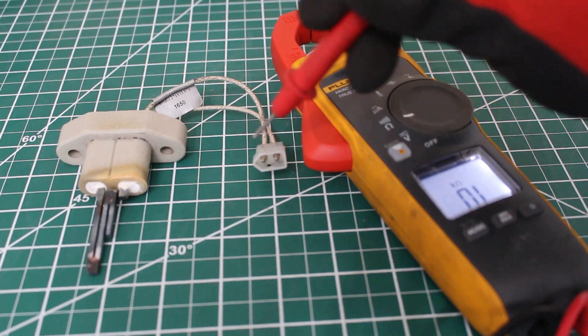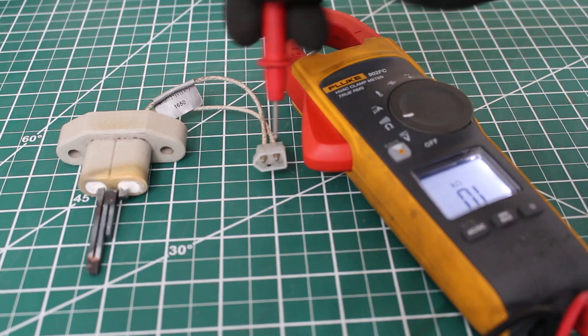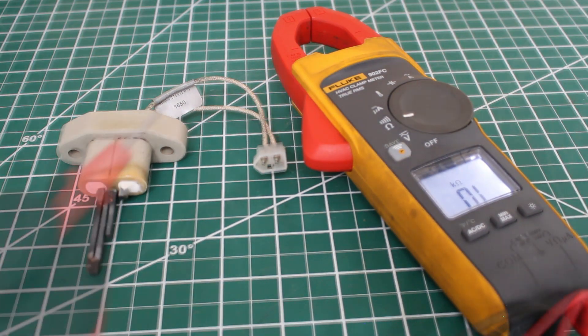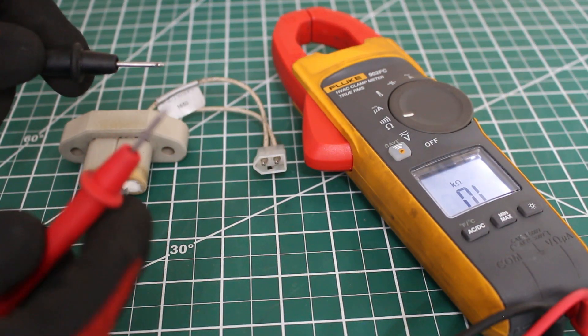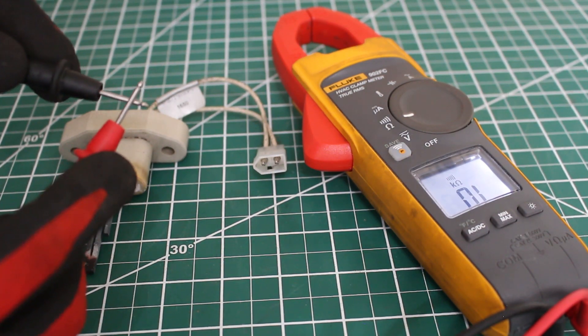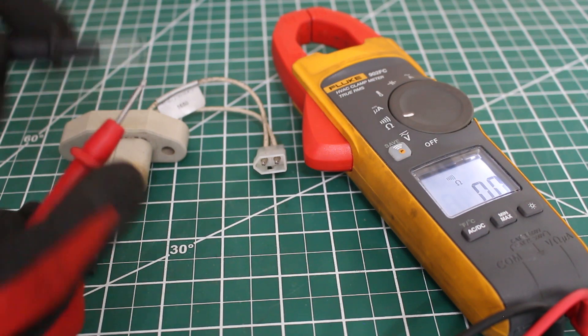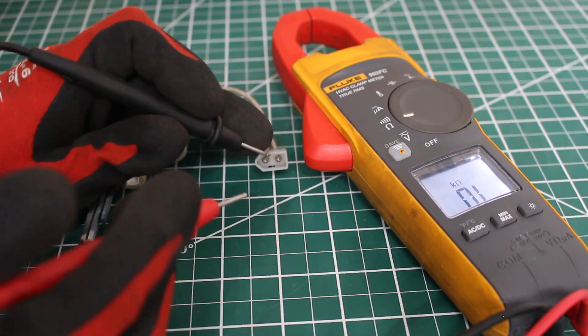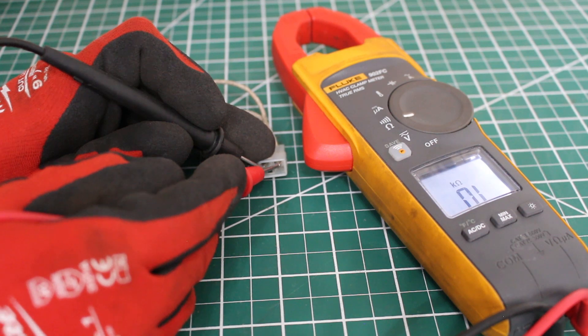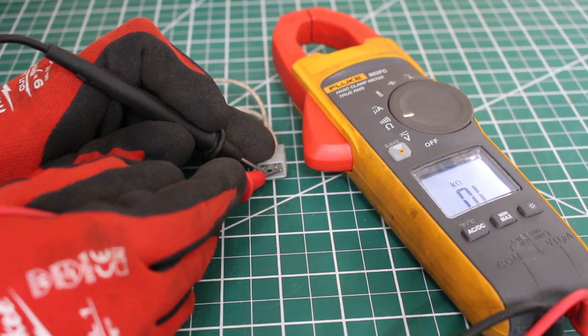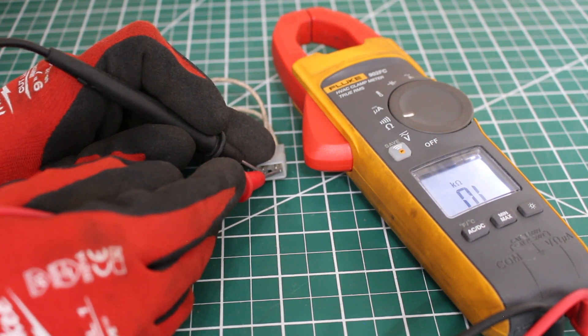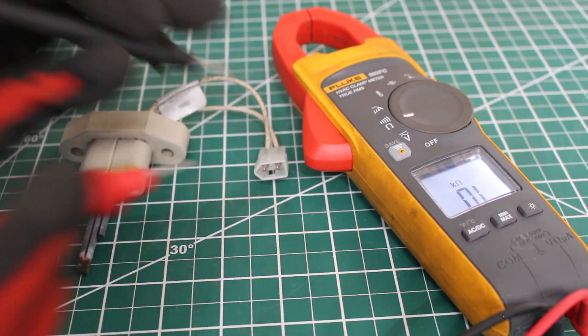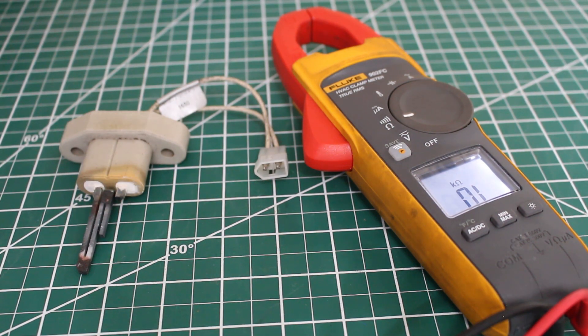So we're going to put our leads across these two terminals. I'm going to short out my leads to make sure they're good. And they are. So we're just going to simply check one and the other. We have an OL reading and this indicates that this hot surface igniter is bad.